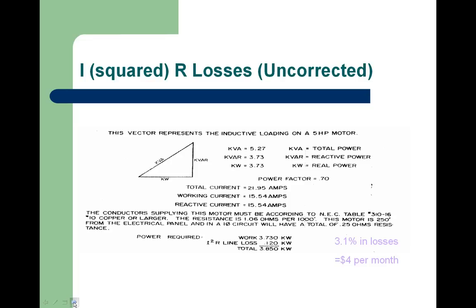If you were to put a capacitor bank on at a main switchboard, and let's say it was physically about 10 feet from where the hydro meter would be, and you were able to reduce your load from 1,000 amps down to 800 amps, there would be very little in the way of heat recovery because the distance is relatively short. Now, if we take that same scenario and we move the 800 amps of load further out into the plant, the I squared R losses, of course, are much greater, and there can be some additional kilowatt-hour savings that capacitors can recover.